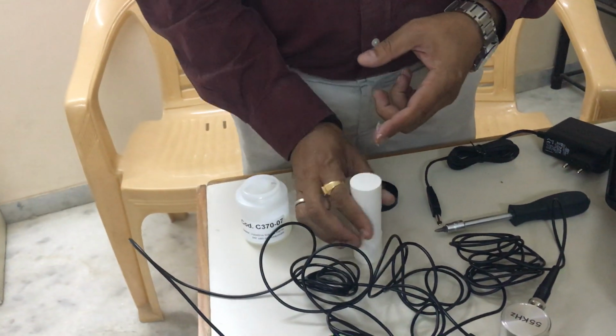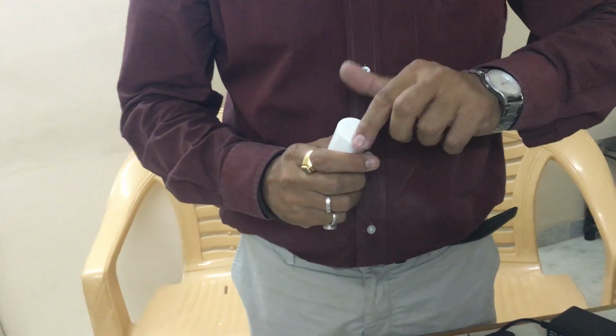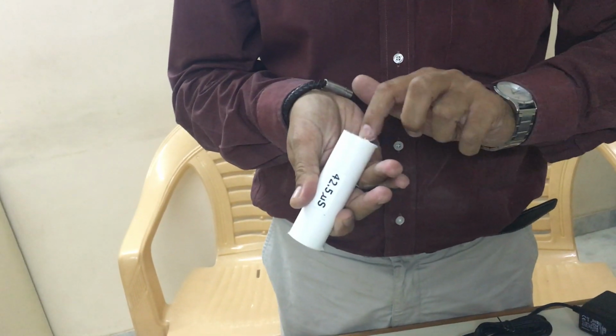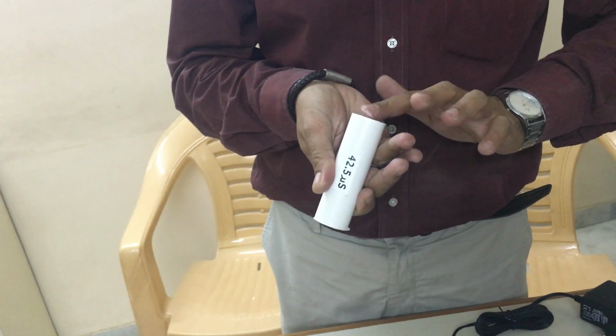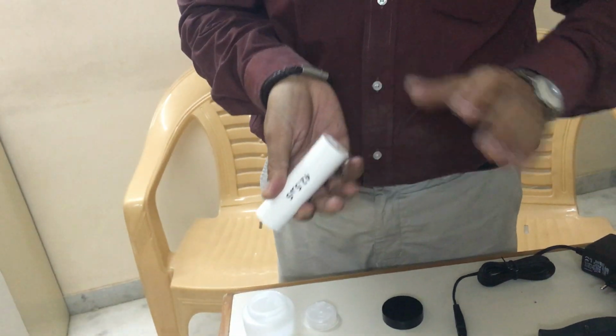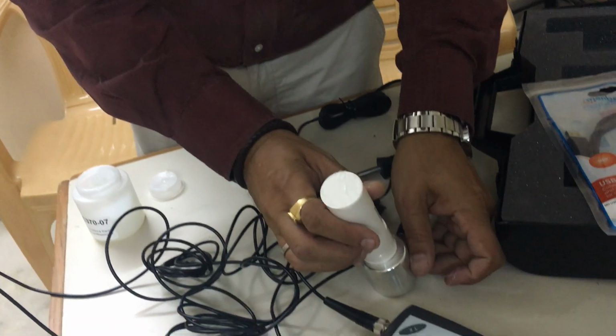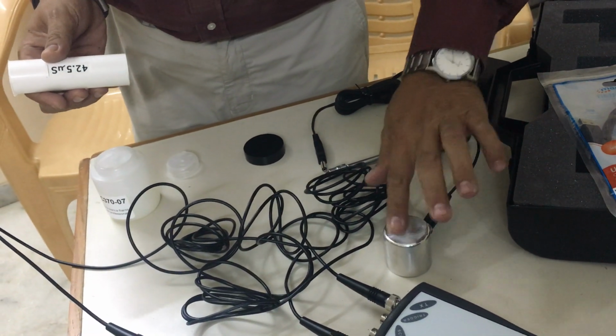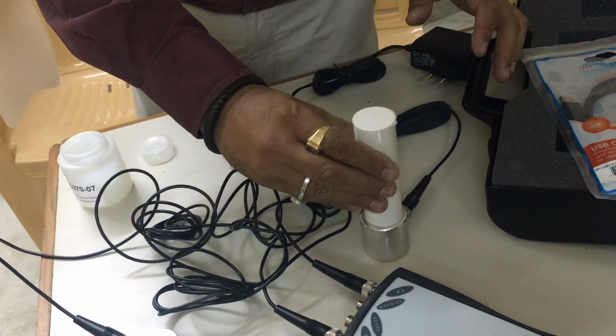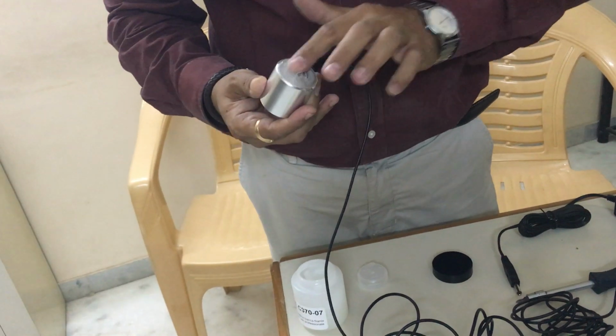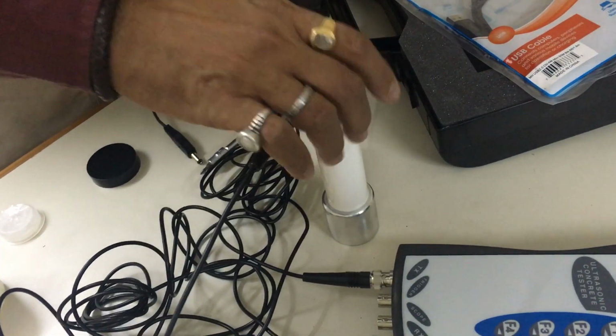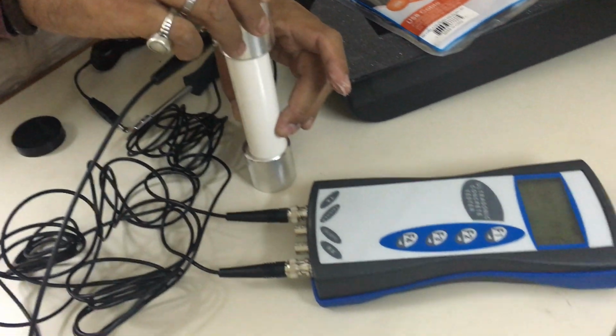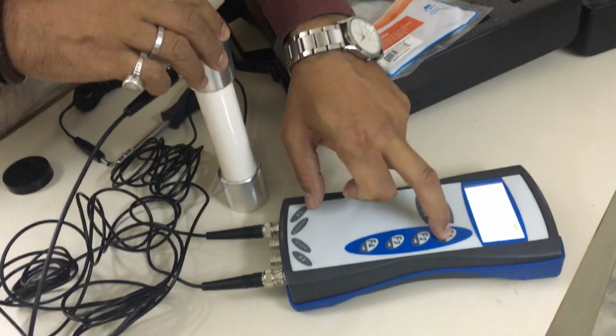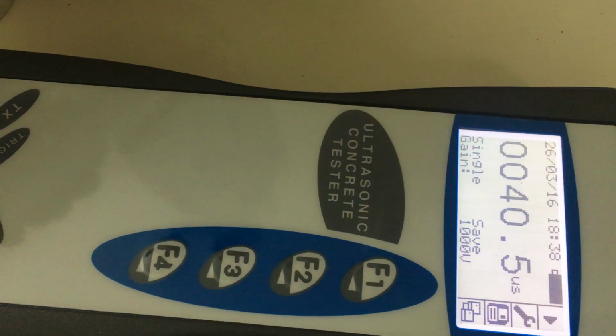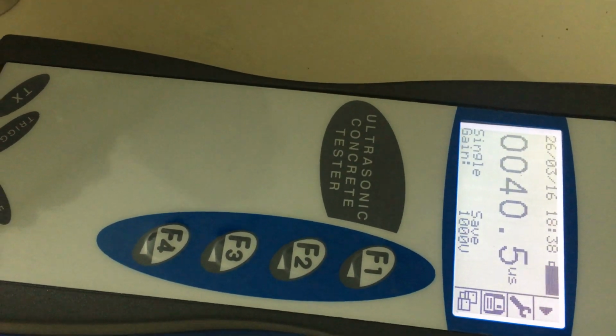The first and foremost thing, apply the couplant, because this acts as a contacting medium, an acoustic contact between two different surfaces, that is your ultrasonic probe and your surface. So I'm applying it on this surface also, and on this surface also, contact medium, putting this. Okay, now I press the start key, that is F1. Okay, it's showing 40.5 microsecond. Actually its value is 42.5 microsecond.